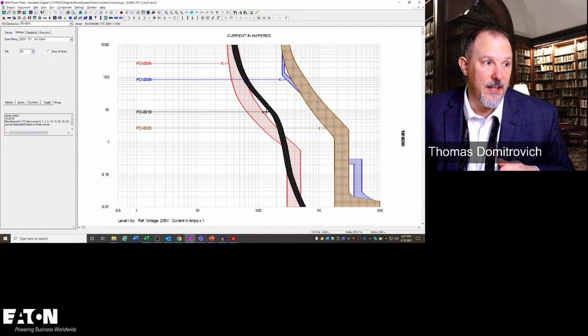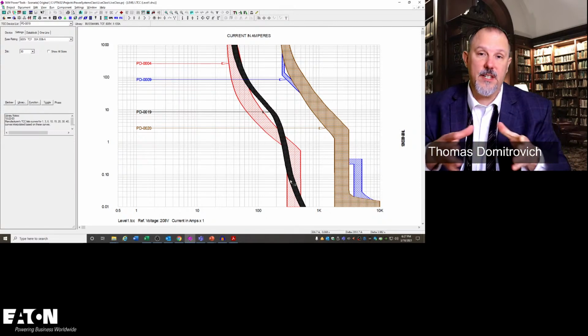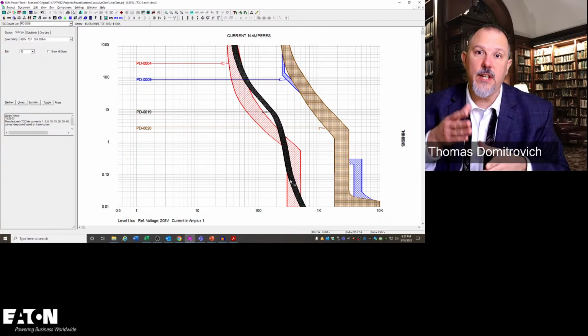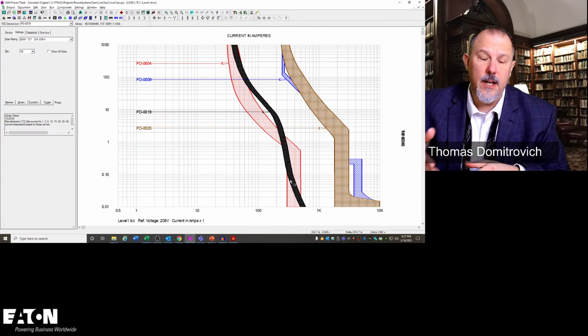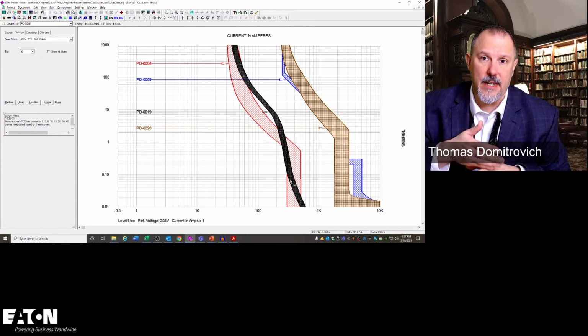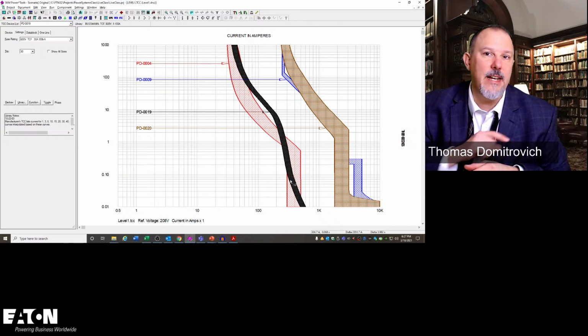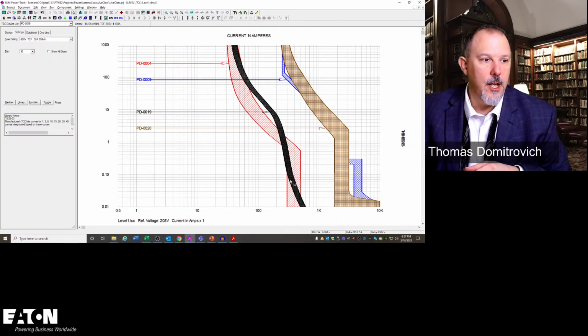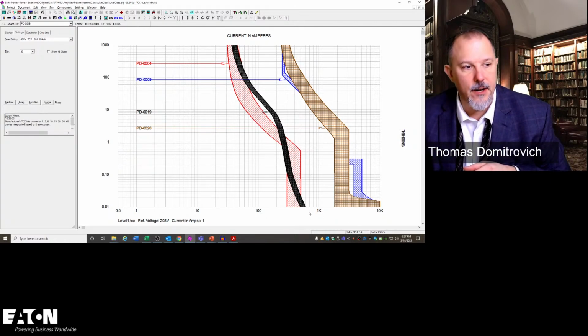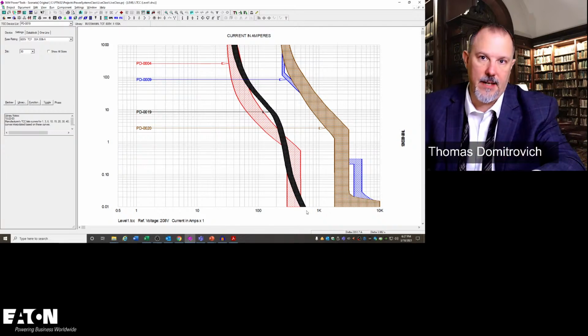I'm going to this fuse, and the reason it works that way is because the fuse acts so fast. I'm clearing in less than a quarter of a cycle. So that breaker didn't even know the event occurred. What we don't show is what's plotted down here, and we don't have to when you have the tables.